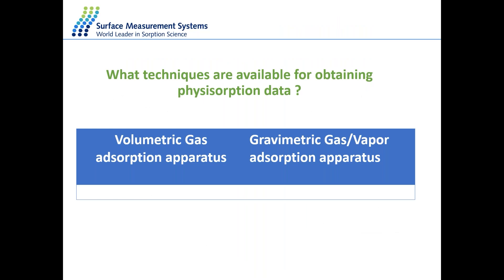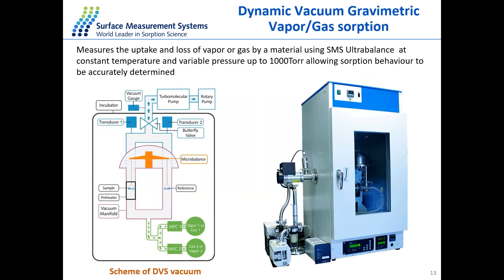How can we obtain physisorption data to characterize the catalyst? There are two main techniques: volumetric gas adsorption apparatus, typically used for BET or porosity measurements, and gravimetric gas vapor adsorption. The main difference is that in volumetric, we measure pressure changes — we dose the gas of interest like nitrogen and wait for pressure to equilibrate. In gravimetric, we continuously weigh the sample during changes in concentration of gas or vapor over the sample. I will mainly focus on the gravimetric vapor/gas adsorption analyzer — in this case, the DVS Vacuum.